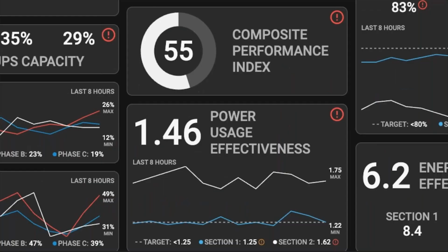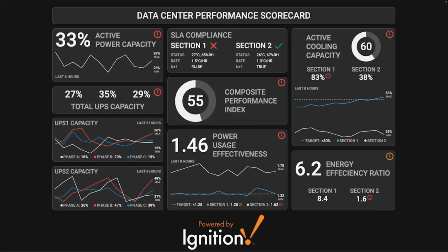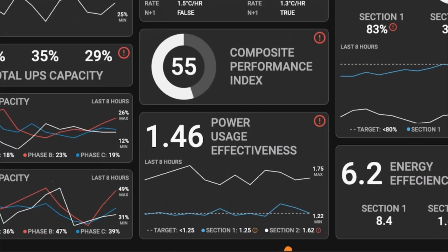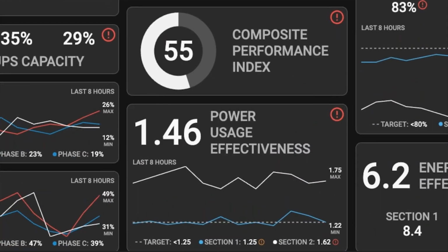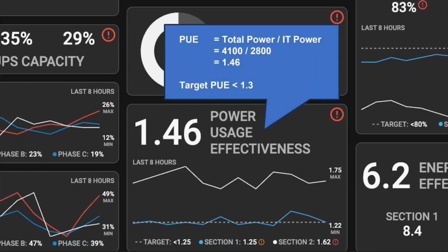Okay, one thing you can do, you can put all that information in a balanced scorecard. So this is a balanced scorecard, again, built in Ignition. In the middle, there's a composite performance index. But if you zoom in to this balanced scorecard, which I will do step by step, it starts with the PUE. You can see that my PUE is 1.46 as shown in my previous story. And you can see the two parts, 1.25 and 1.62 for the two rooms. And so together it will follow the PUEs.